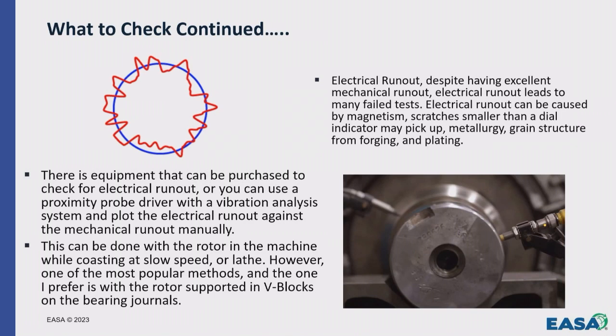They can connect to an analyzer, and then in that particular picture, this is a machine made for it. On the left is a mechanical run-out sensor, and on the right is an electrical. What they'll need to do is set up a prox probe parallel to the mechanical run-out, and then compare those and overlay them against each other. And that's how you check for the electrical run-out. It's easier with the purchased machines, but they are a little pricey. So I mentioned we could do it in the machine on coast down, but one of the most popular methods is in V blocks after disassembled.